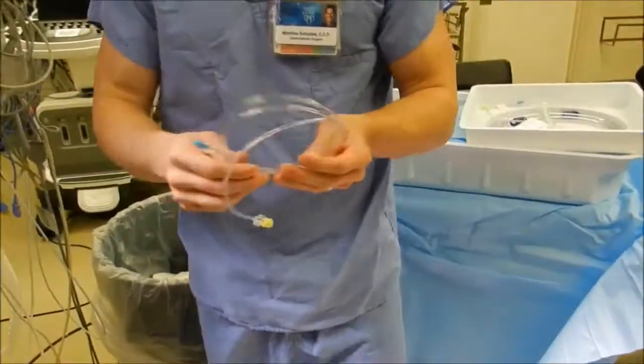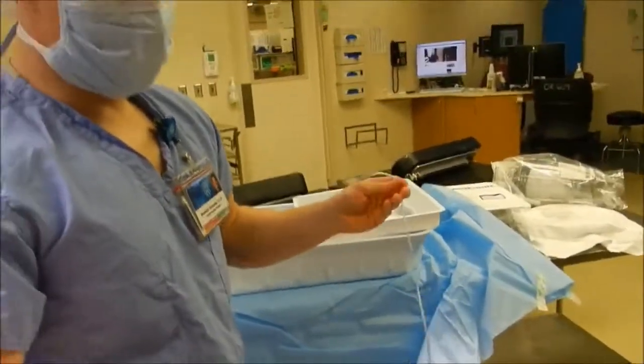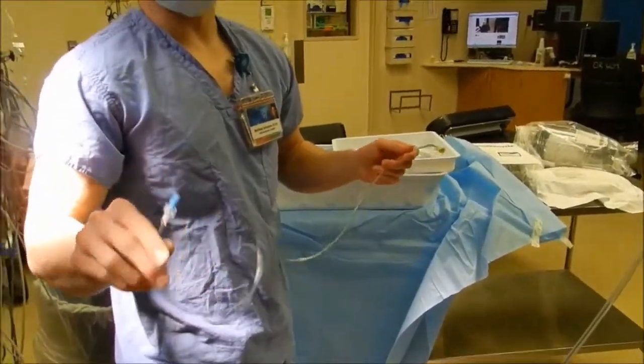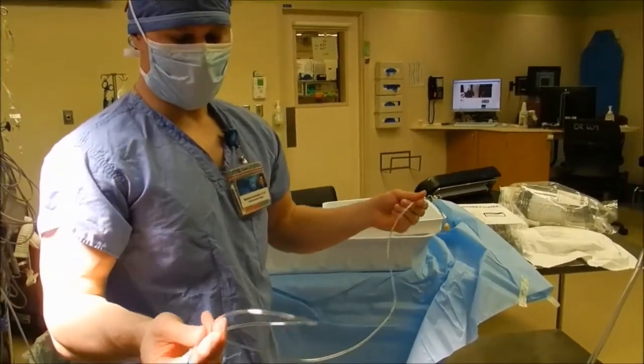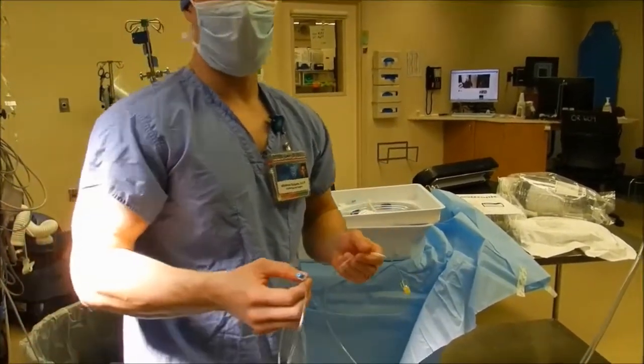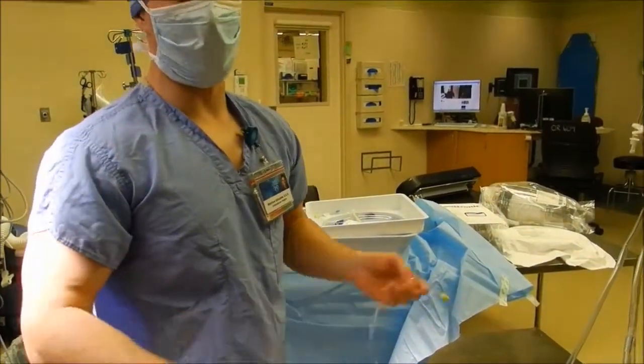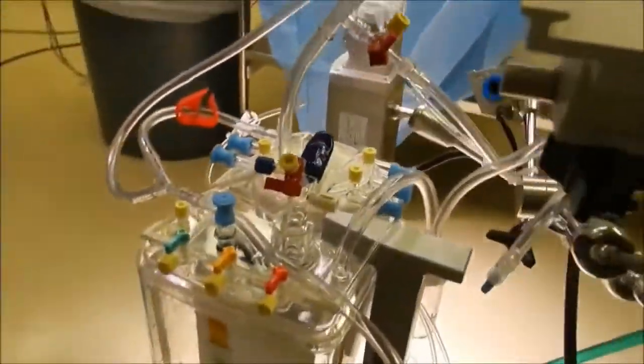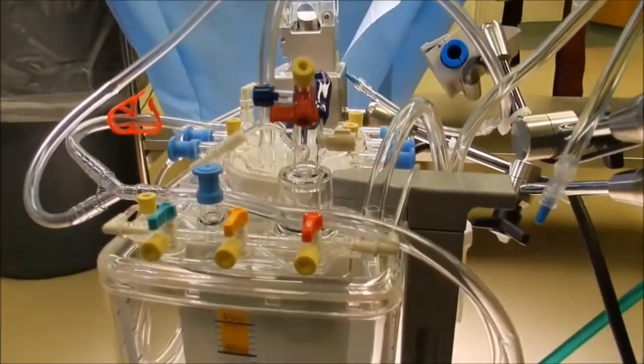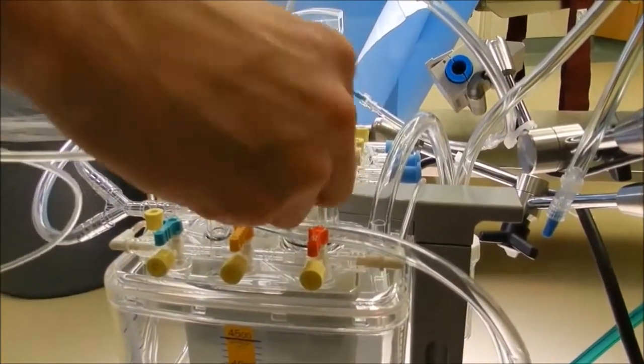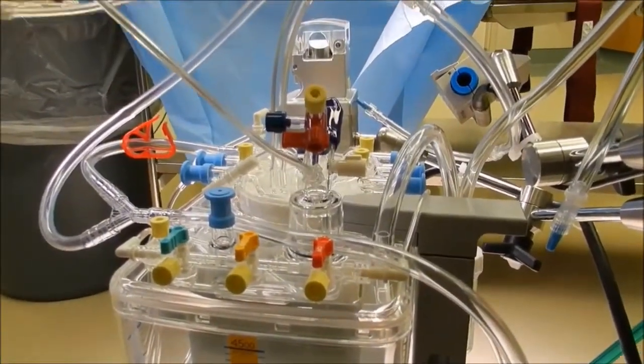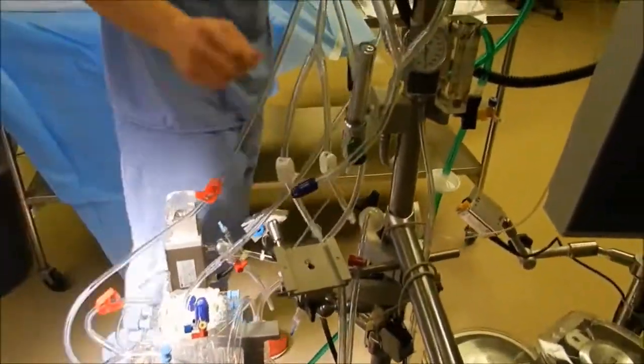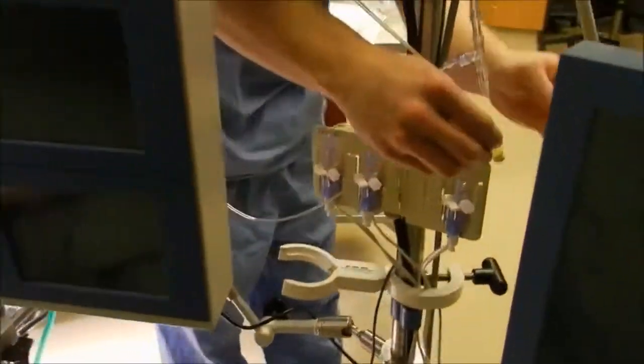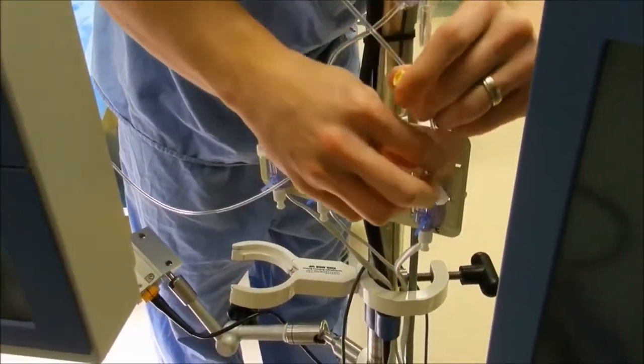When you run vacuum, you should always measure your negative pressure. We use vacuum, I'd say, in almost 99% of our cases for our surgeons. So we measure off of our venous inlet instead of off the top of the venous reservoir. It gives you a true measure of what your venous pressure is. So that gets plugged into our venous inlet on our reservoir. And then we will plug that into our venous transducer, which is over by our other transducers for both cardioplegia and arterial line.